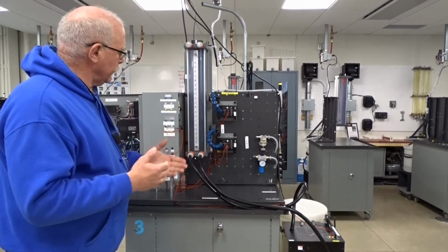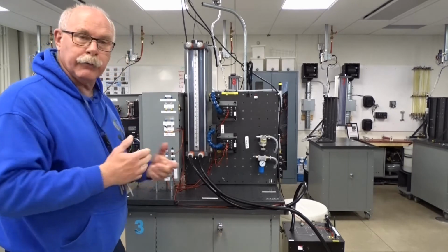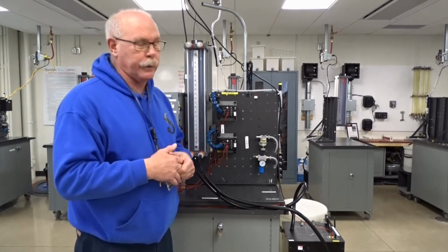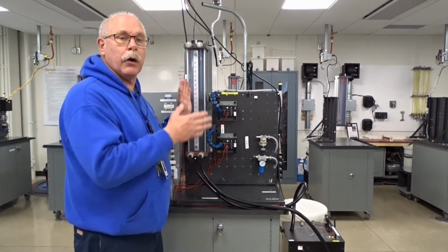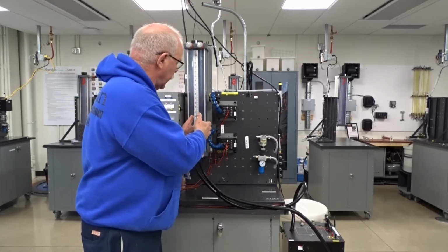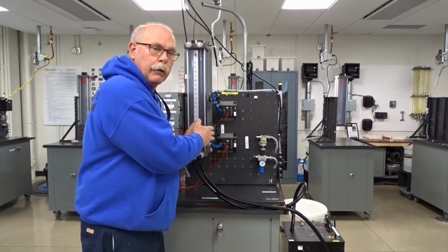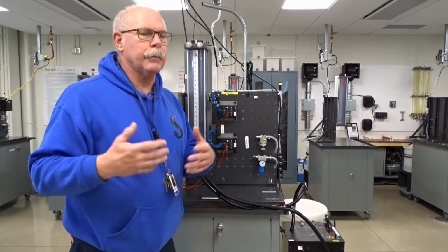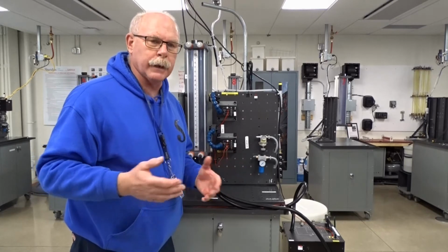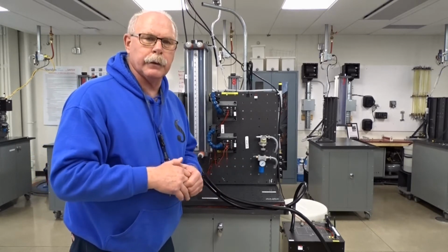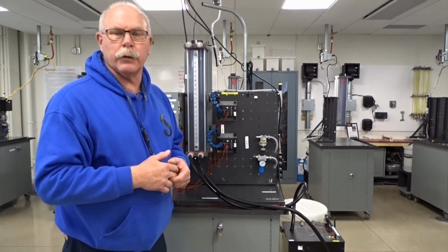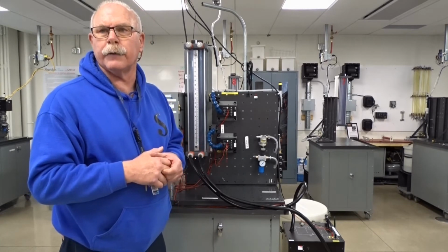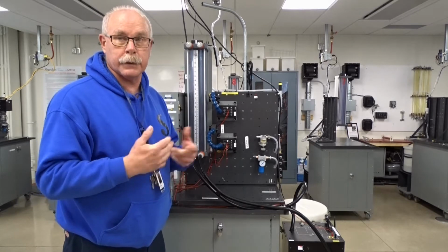So this type of detection of level is called a direct level measurement. It's because these capacitance switches actually are reading the water itself. We're not using some other aspect of this process and trying to determine the level by calculation. Okay, so let's look at the parts of this system itself.